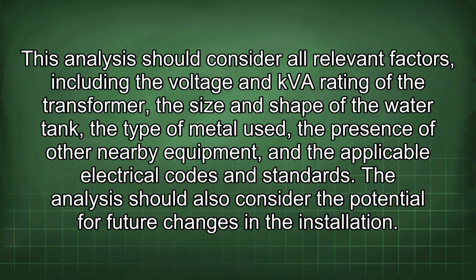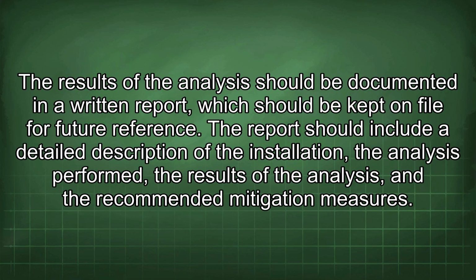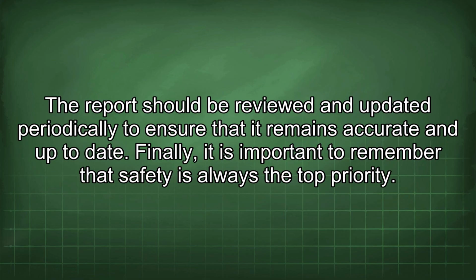This analysis should consider all relevant factors, including the voltage and kVA rating of the transformer, the size and shape of the water tank, the type of metal used, the presence of other nearby equipment, and the applicable electrical codes and standards. The analysis should also consider the potential for future changes in the installation. The results of the analysis should be documented in a written report, which should be kept on file for future reference. The report should include a detailed description of the installation, the analysis performed, the results of the analysis, and the recommended mitigation measures. The report should be reviewed and updated periodically to ensure that it remains accurate and up to date.